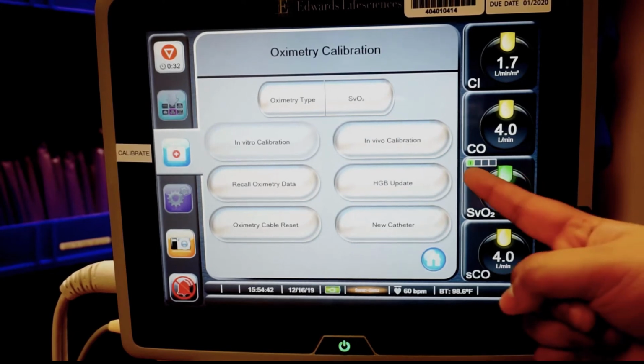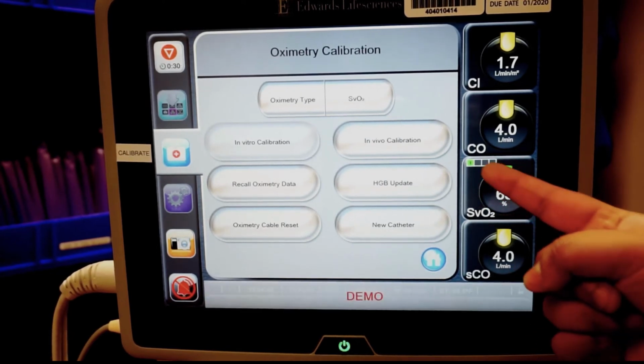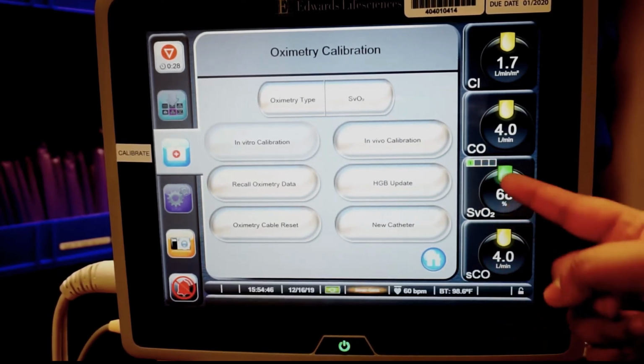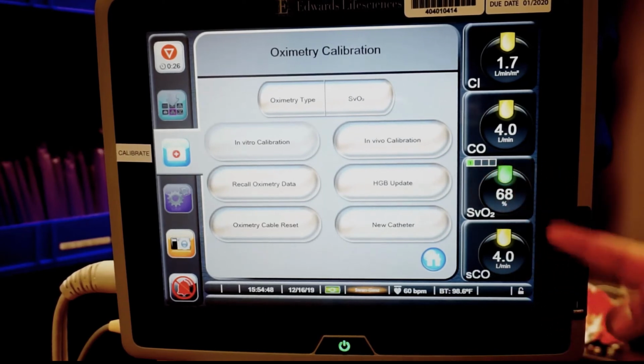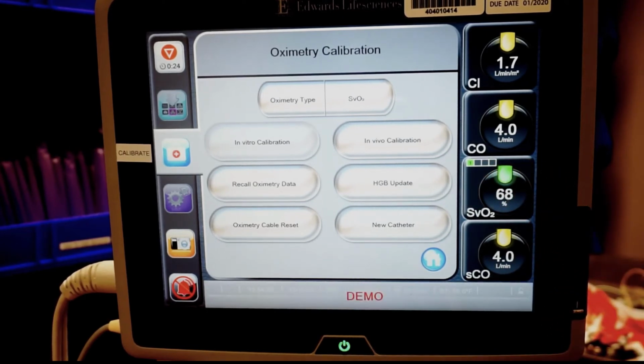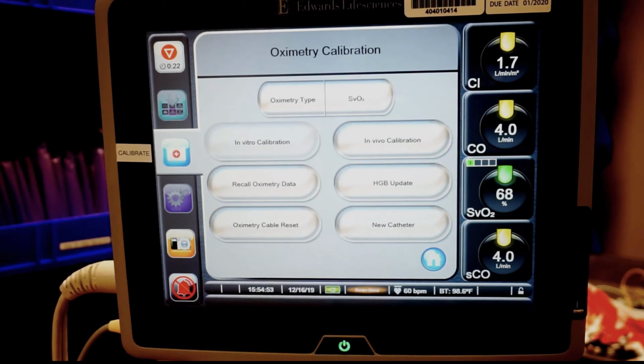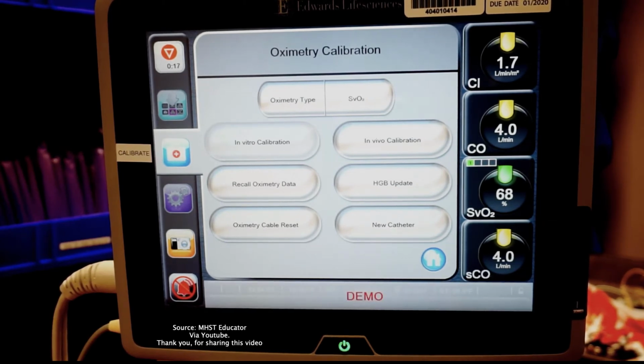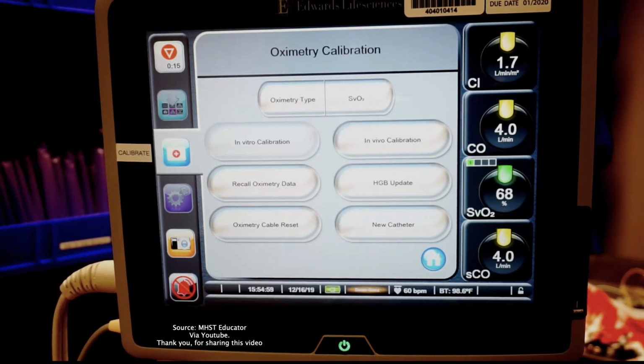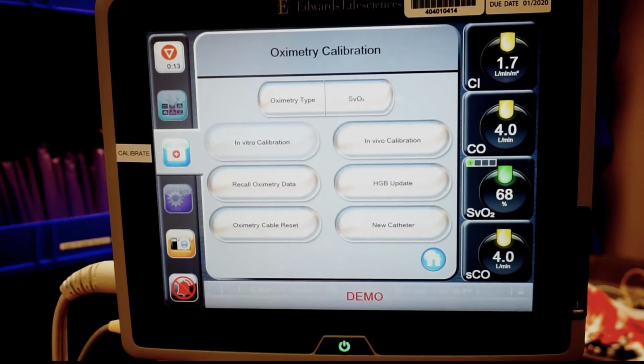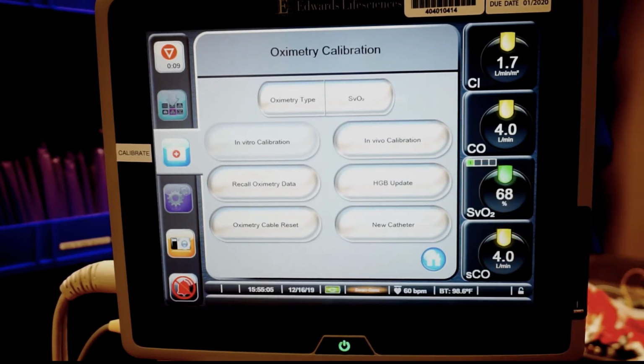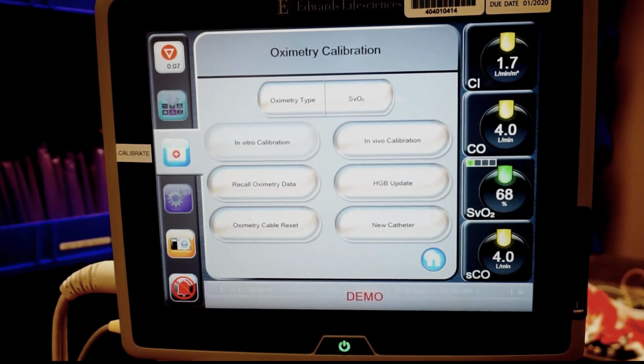On my SVO2, I can see there are 4 boxes here. Got 1, 2, 3, 4. If I have 4 boxes filled up, essentially what that means is I'm not getting an accurate reading. Maybe the end of my line is on a vessel. Maybe the cord is just reading inaccurately, it's an old cord or it's an old swan, and so it's not reading accurately. What you're going for is that 1 to 2 boxes. 1 to 2 boxes means that it's going to be accurate.